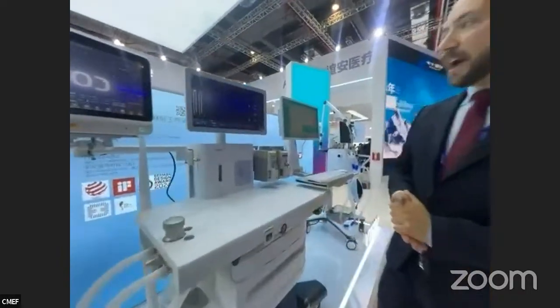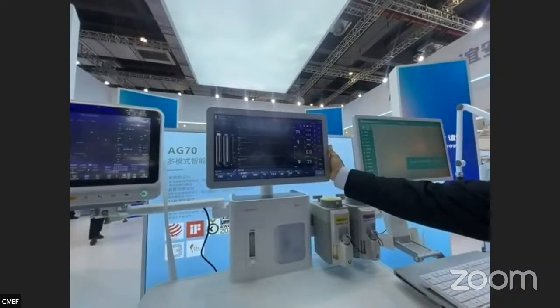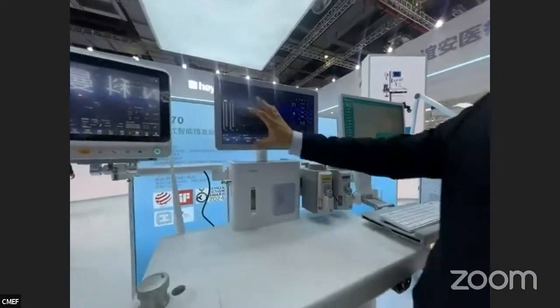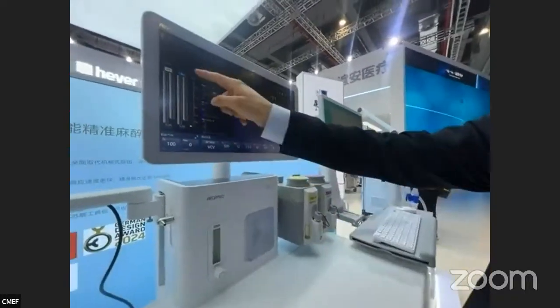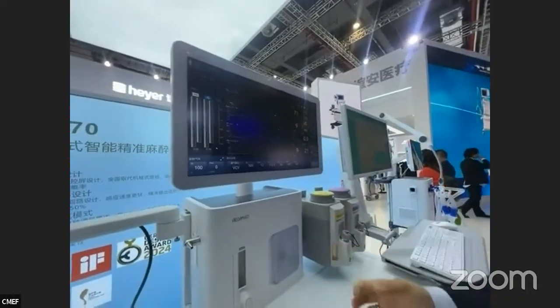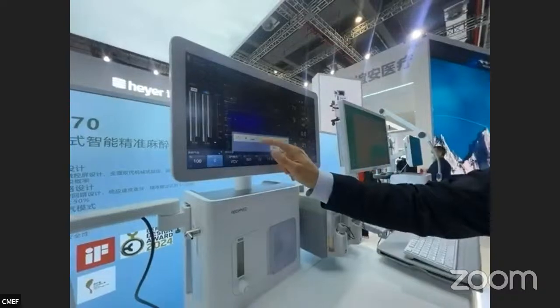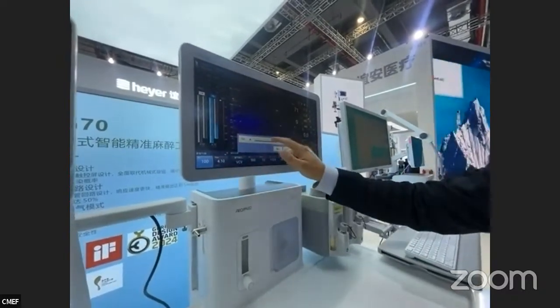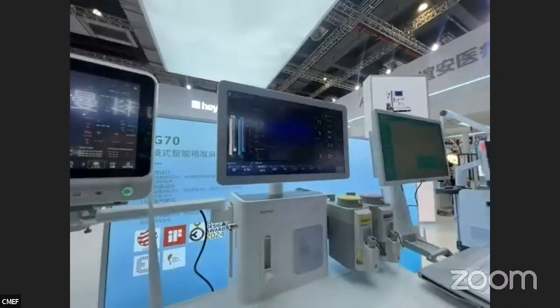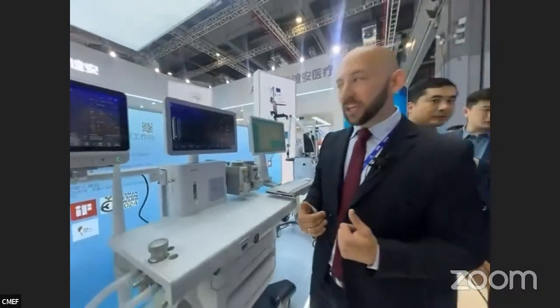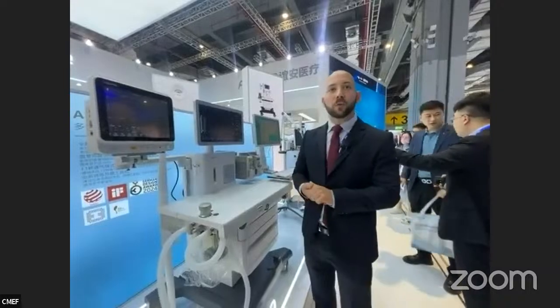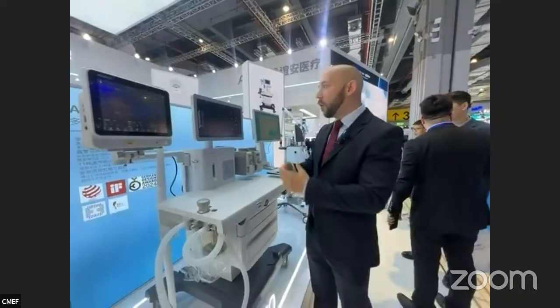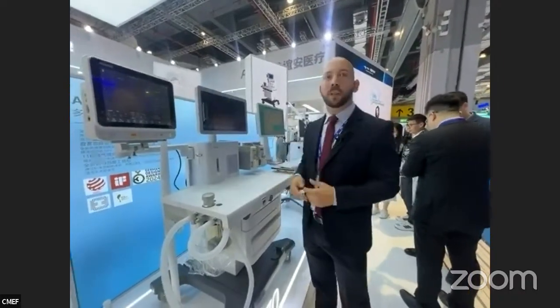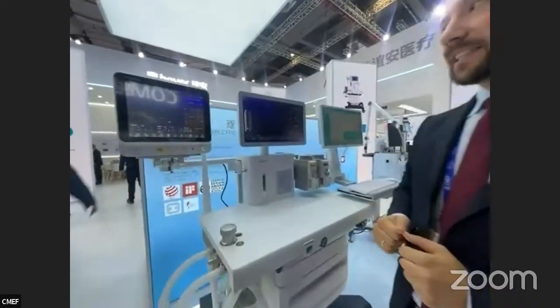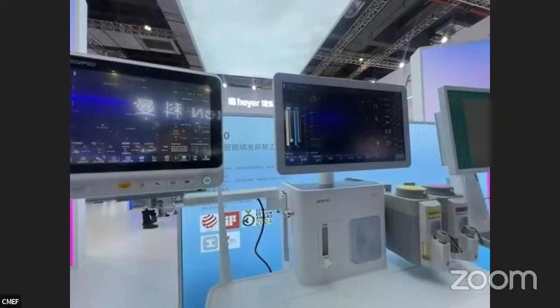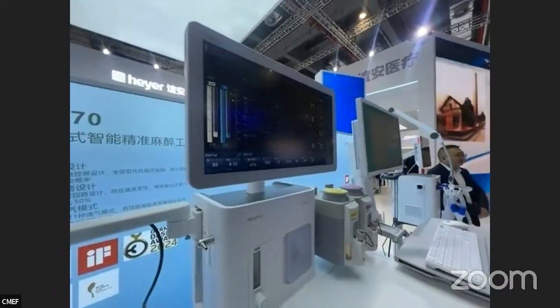Now, when we look at the device itself, again, we have a very easy interface and an adjustable monitor, but the first thing that we could talk about is our electronic flow meter. The electronic flow meter allows you to adjust the flow of the gases by yourself, and you have the choice to set the total flow that you want to give to your patient. You can set the oxygen concentration, and the machine will automatically adjust the flows of the corresponding gas. Of course, depending on the patient, maybe some flows will be too high or too low.